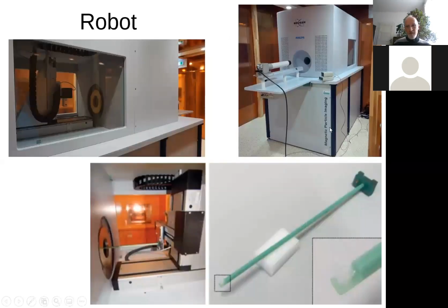The machine itself is pretty complicated. Here inside is the magnet which creates the gradient field together with coils producing alternating drive field. Here in the back, looking through this window, is a robot which enables placing a rod with the sample and moving it back and forth, up and down, left to right for calibration.